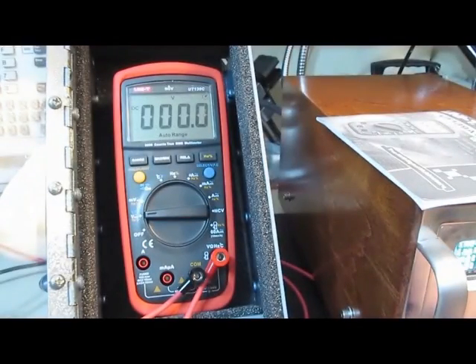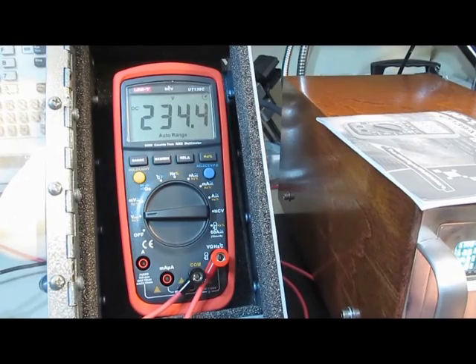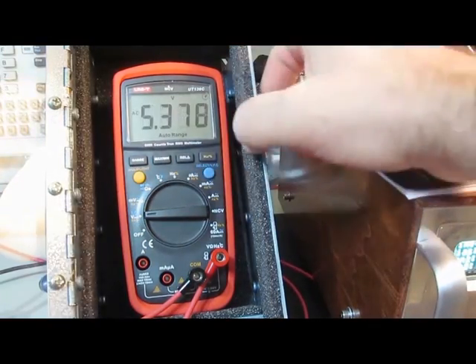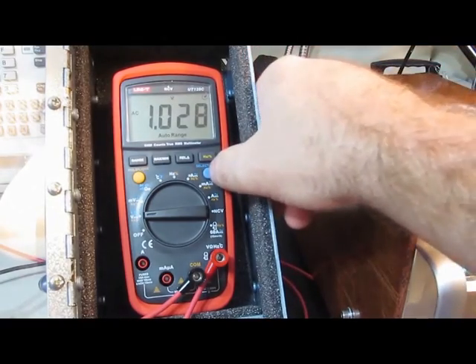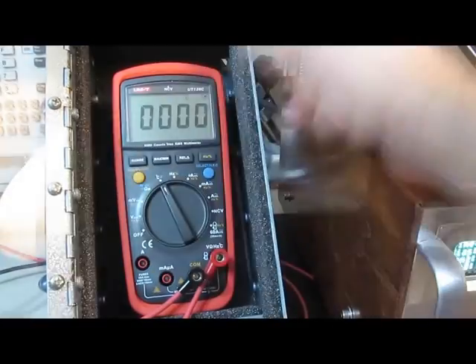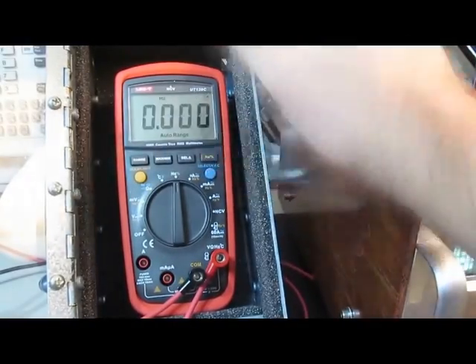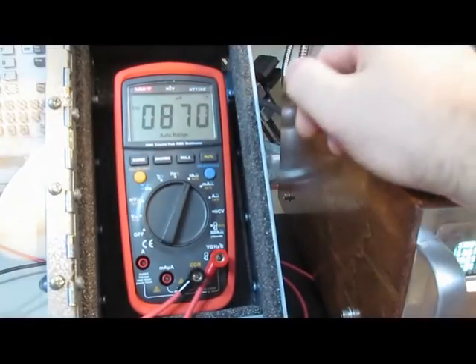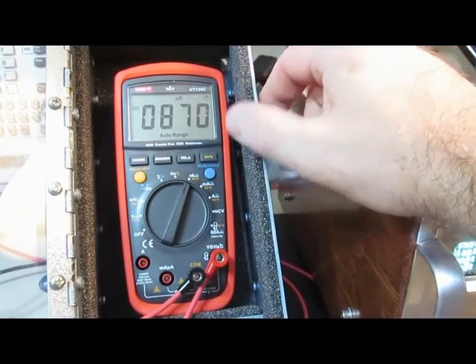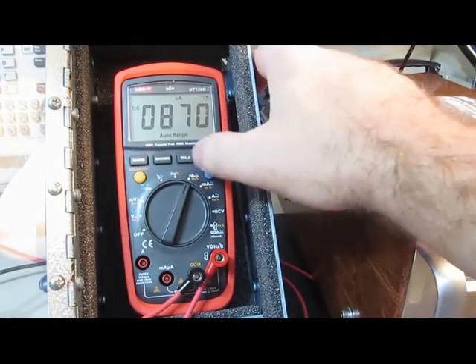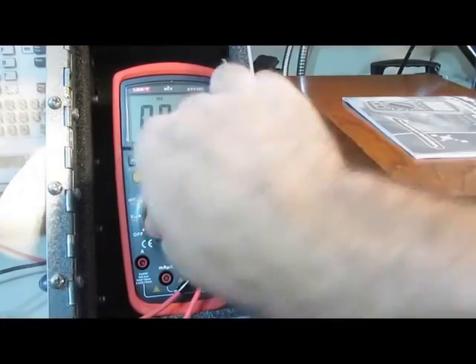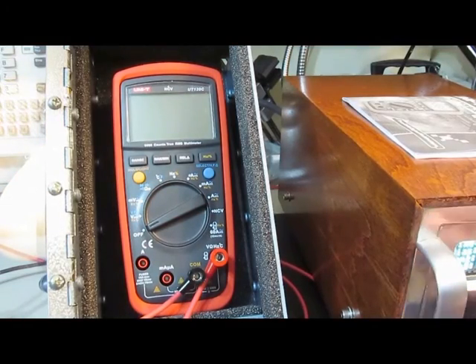Okay, the output of the box now is live. And you can see we are definitely putting out some type of voltage. This is in DC mode right now. Here we're in AC, again it is a rectified signal. Actually surprised I can't pick that up. I wonder how they do their frequency measurement. It may require a zero cross or something. That's all there is to it. So we'll go ahead and functional test it, see if it still works.